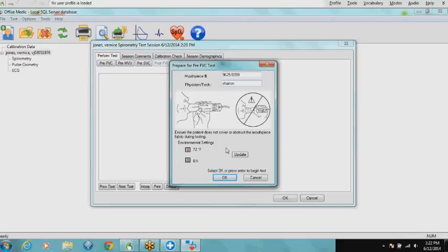All right, so before we click on OK, I'm going to walk you through what's about to happen, and we're going to have the patient perform the maneuver. Here's what's going to happen. When we click on OK, the device is going to attempt to find zero pressure movement. So we don't want to move the mouthpiece. We want to just keep it still. It's going to flash yellow and green until it finds a zero baseline condition, meaning we're ready to take a test. Once it does that, it displays 2 green circles as preparatory, and then it will display the actual incentive graph.